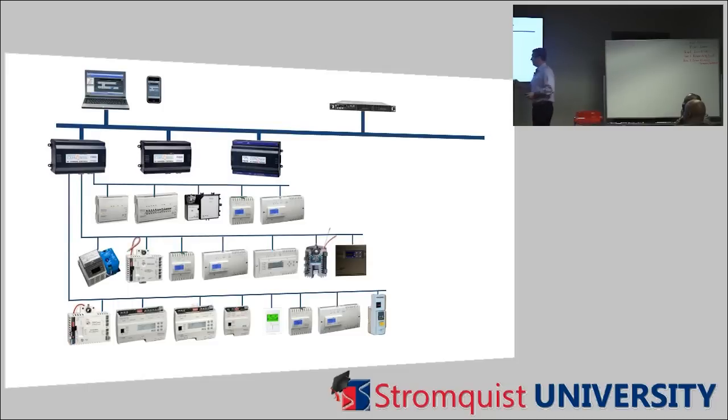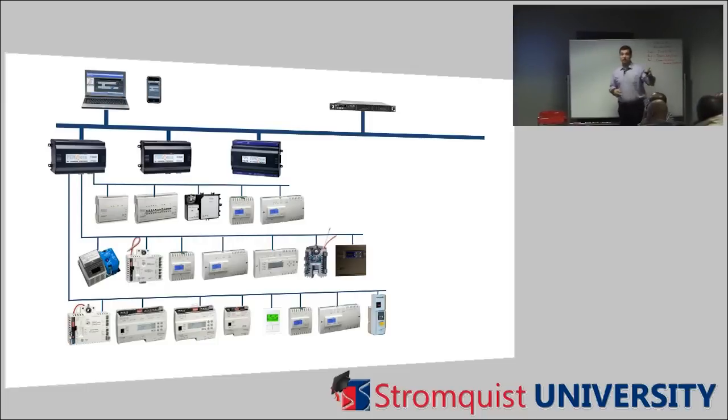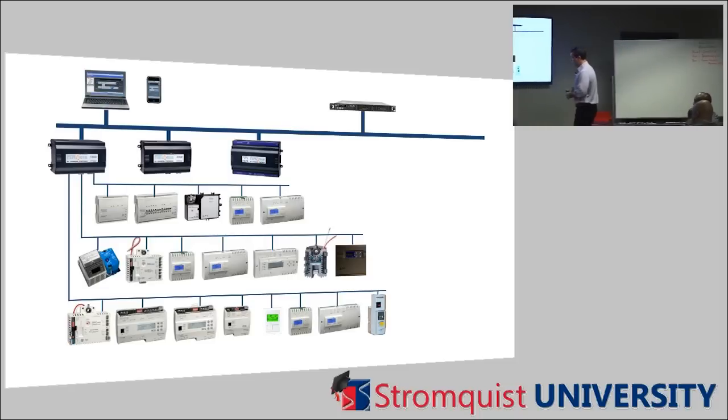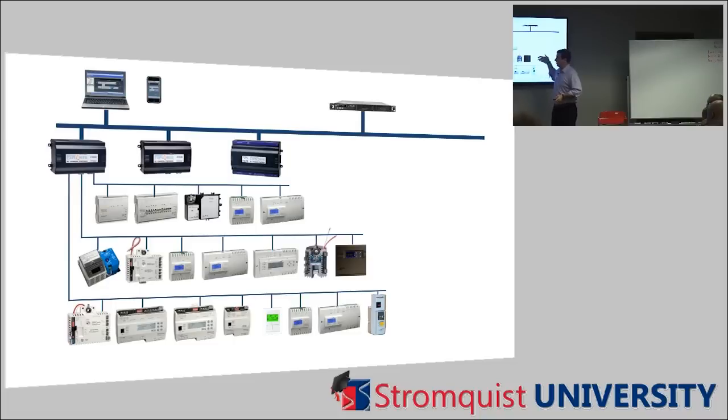Now we've got our BACnet and LON all pulling into that one Jace. We're not going to get rich because it's already been made. And now it can all talk to each other. So in your situation, one of two things is going on in your building.